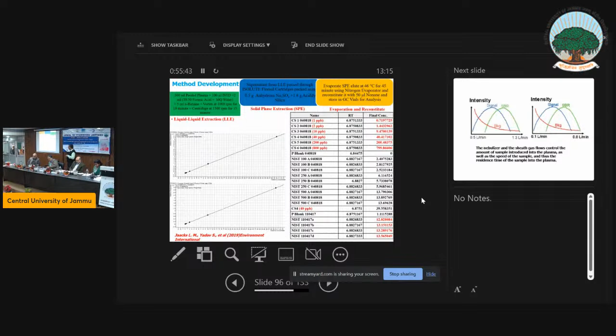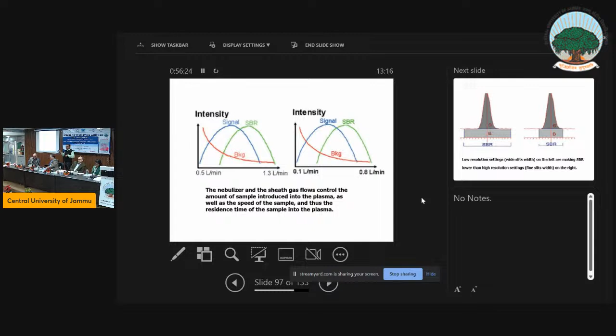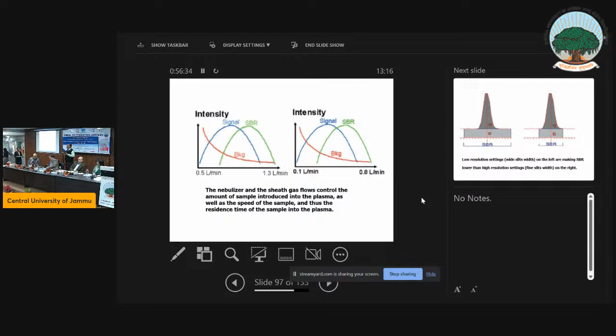So last, when you talk about ICP-MS, another 2 minutes I will take maximum. What is the flow rate? Signal and signal to background ratio. Now the signal is going up, but the background is also going up. The nebulizer and sheath gas flow control the amount of sample introduced as well as the speed, thus the residence time of the sample in the plasma. So when you do this analysis on ICP-MS, you have to go to the literature and see what sheath gas I want, what nebulizer flow I want, because the analyst will tune it for his own purpose. Like Shweta is using, suppose I am using, I tuned the flow rates to my own requirements. For you, it may not work. So it will depend upon these parameters.